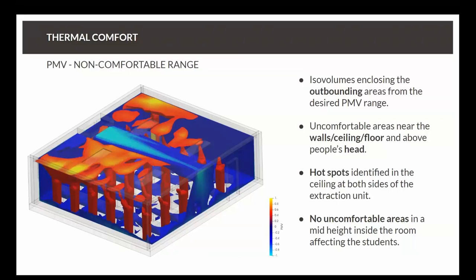With this scary picture, I just want to show you where these uncomfortable ranges from the PMV variables would be, so I'm just plotting volumes with values higher than 0.5 and lower than minus 0.5. So despite how scary the picture may look, you can see that inside the room, there are no volumes of hot spots or cool spots. More maybe in these corners we were talking about before, but in the room, it looks pretty fine. I think that some of those will resolve themselves as well if we make some changes to the model on the distribution. Exactly. Some of those areas will be reduced, but the standards that we look at in the UK focus largely on the occupied zone anyway. I don't think, the only reason why you'd want to know what was happening at the ceiling height is what effect it has on the occupied area. It doesn't really matter otherwise.